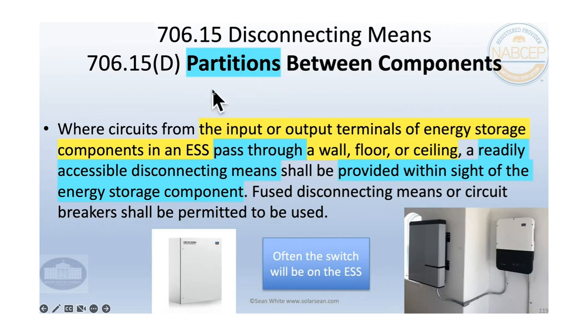And so, partitions between components, energy storage passed through a wall: a readily accessible disconnecting means shall be provided within sight of the component. And so this was another question that somebody was having. If we have these different components, it's not an energy storage system, but if you're going through a wall, then you would want to have a disconnect for each component. So this does have a switch on it, and I would consider that a disconnect going through a wall to here. The thing is, you can see just in this picture too, there's no code requirement to have a big, huge load break rated disconnect here.